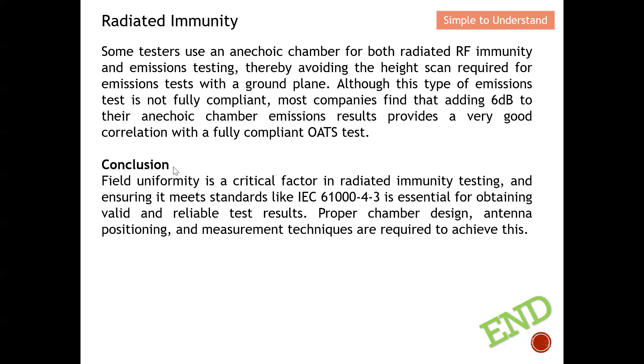In conclusion, field uniformity is a critical factor in radiated immunity testing, and meeting standards like IEC 61000-4-3 is essential for obtaining valid and reliable test results. Proper chamber design, antenna positioning, and field management techniques are required to achieve this. Thank you, please like and subscribe, and I hope to see you soon.